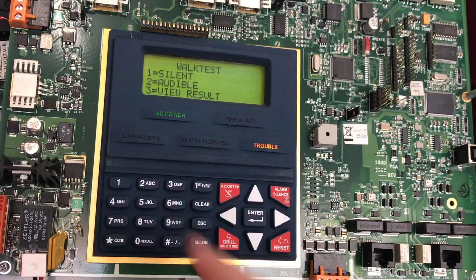The main goals of a fire alarm inspection are to ensure complete, total operability of all components of the fire alarm system, including initiating devices, horn strobes, whatnot. What I will do is first go to the panel and take the system offline with monitoring, so it's not going to end up sending the fire department once I start sending signals in. Then I usually put the system in walk test, if the setting allows for that.